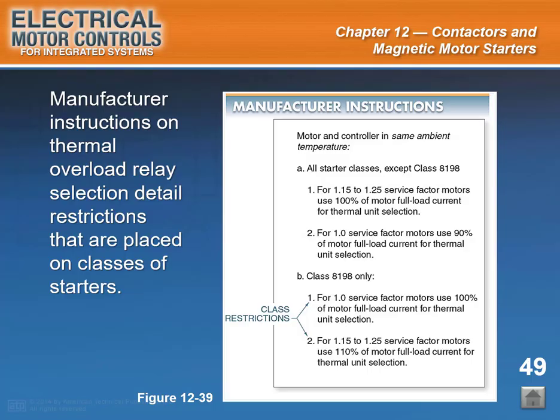Start of slide 49. Slide caption: manufacturer instructions on thermal overload relay selection detail restrictions that are placed on classes of starters. See figure 12-39. It is important to always refer to the manufacturer instructions on thermal overload relay selection to see if any restrictions are placed on the class of starter required. For example, unless a Class 8198 starter is used, motors with service factors of 1.15 to 1.25 may use 100% of the motor full load current for thermal overload selection.